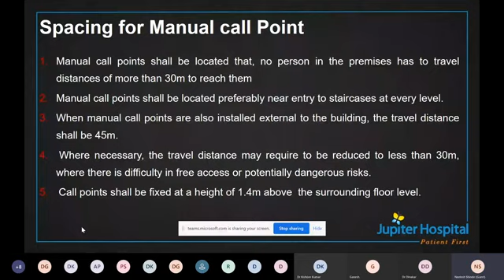Now there are manual call points also. A manual call point shall be located so that no person in the premises has to travel a distance of more than 30 meters to reach it. In case of fire, we normally say that we have to switch off lights and everything. So it should be accessible so fast that we should not have to travel more than 30 meters to access it. Normally it is always kept near the staircase of every level. If it is at the external of the building, then the travel distance shall be 45 meters. When necessary, the travel distance may need to be reduced to less than 30 meters when there is difficulty in free access or a potentially dangerous risk. And the call point shall be fixed at a height of 1.4 meters above the surrounding floor level. So this was for the manual call point.